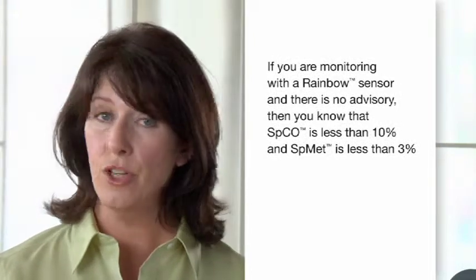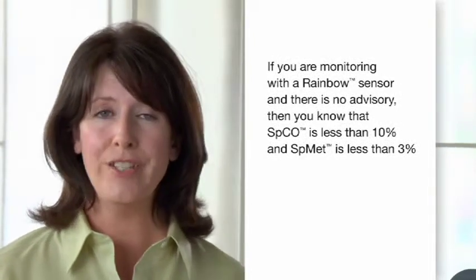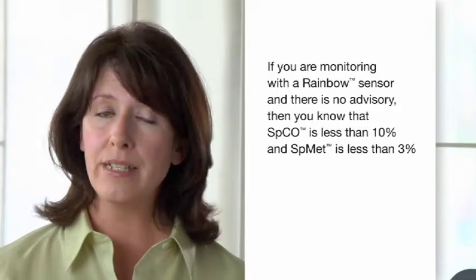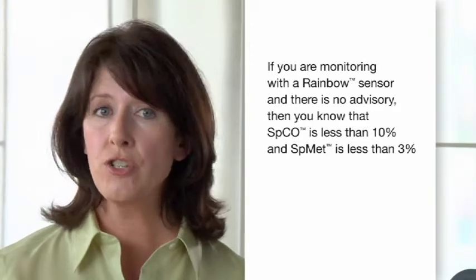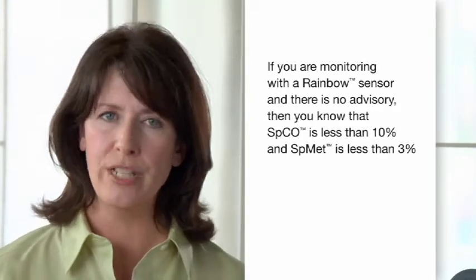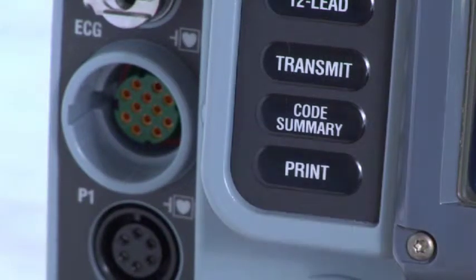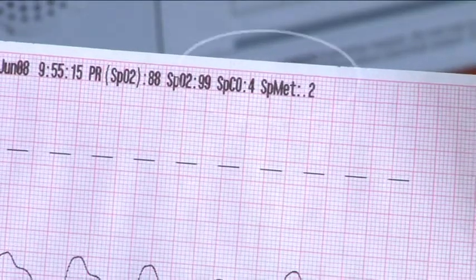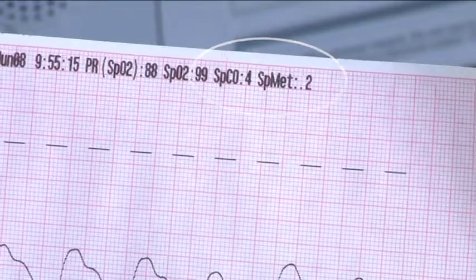So, if you are monitoring with a rainbow sensor and there is no advisory, then you know that the patient's CO is less than 10% and MET is less than 3%. But if you want to check those actual readings, there are two ways to do it. You can press print and get a printout of the vital signs. You see the CO and MET values up here on the strip.